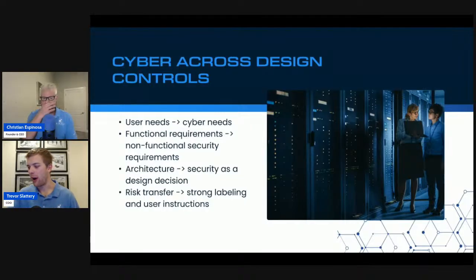Going back to your point on requirements, one easy way I remember how the different types of requirements tie in is that the functional requirements are what your product does, and the non-functional requirements are how it does it. An example: a functional requirement of your product is that you have an imaging system and you have to log into the imaging system. The non-functional security requirements are how you're logging into the imaging system. You might need a password with 12 characters. You might need a one-time pass on your phone or a code sent to your email, something like that. So it's not affecting what happens, but it's affecting how it works on the back end.